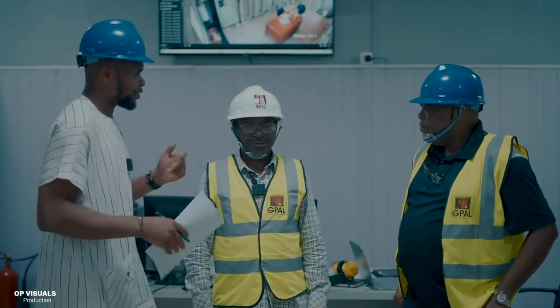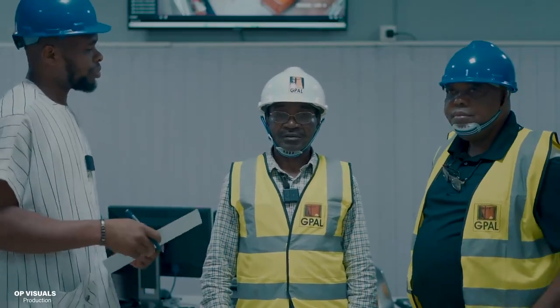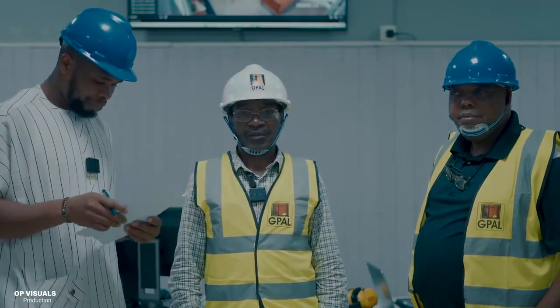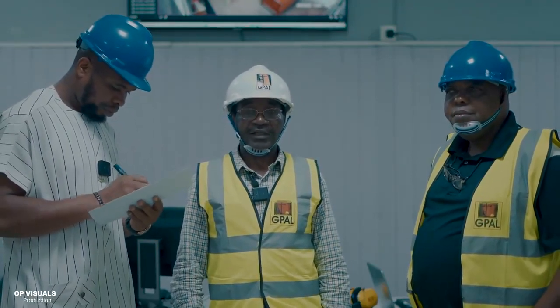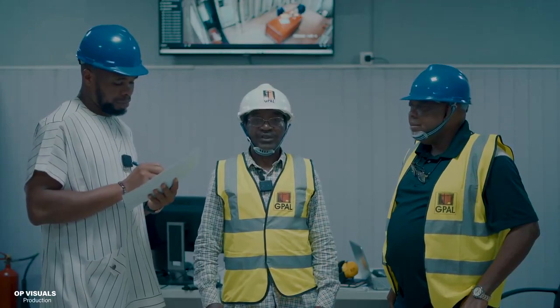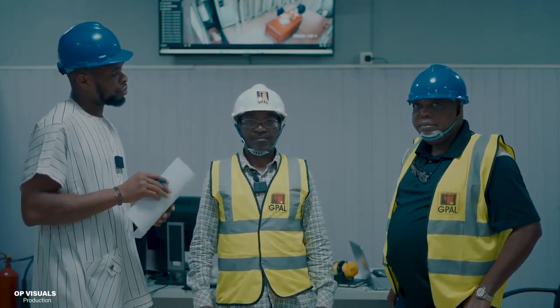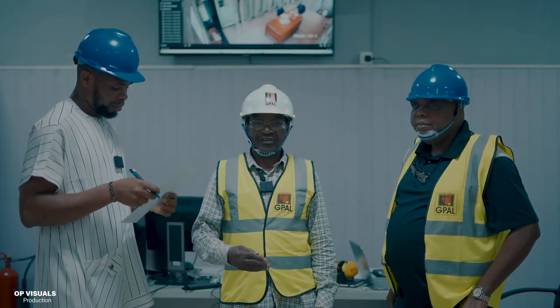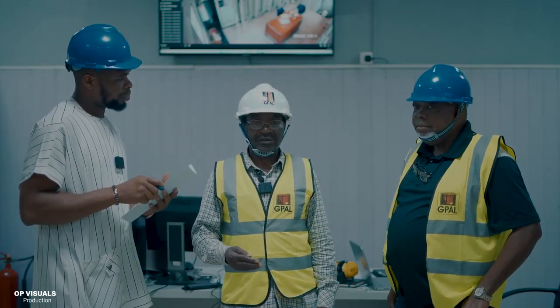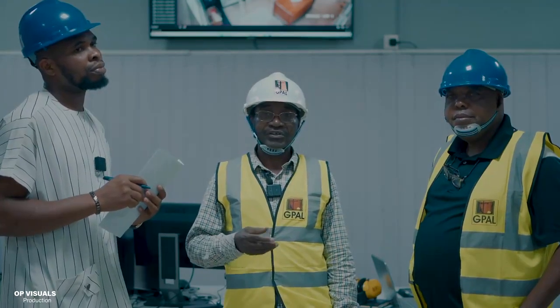Yes. So we have 3 gas turbines, each rated 47 megawatts. All these 3 gas turbines have been test run to full speed, no load. And we started loading them. So power is being released from the gas turbines to the ring-fenced area. But it has to be on a step-by-step basis, because large generators need to go through a process before they reach full load.